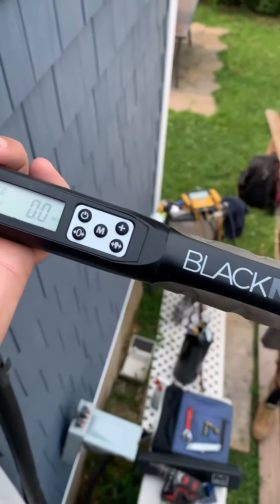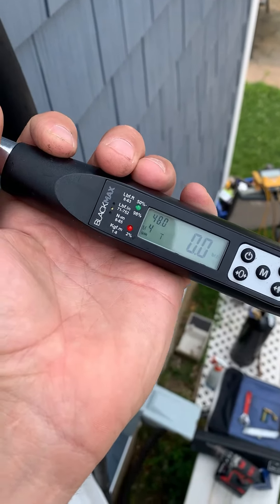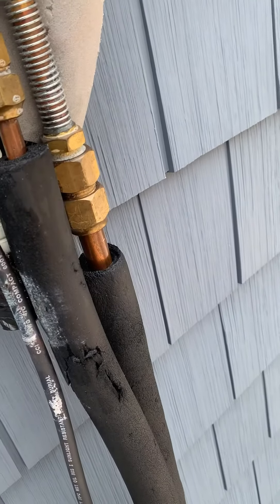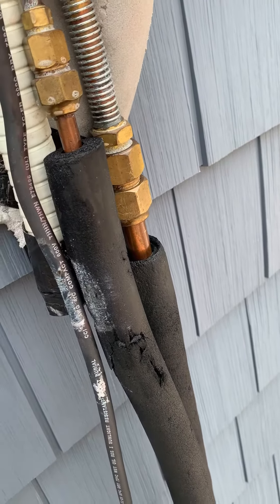We're using the Black Max torque wrench here — this is an awesome tool for mini splits. We set this at 48 foot-pounds because that's a three-quarter inch fitting and the spec is 48 pounds. It'll let us know right when we hit 48 pounds of torque so we don't over-tighten or under-tighten the joint.